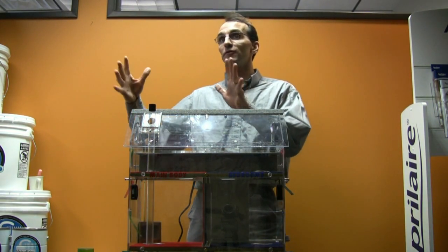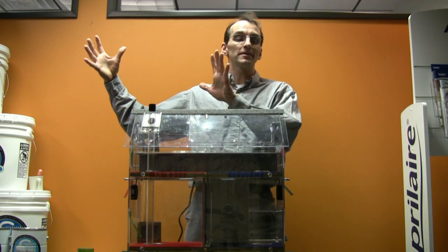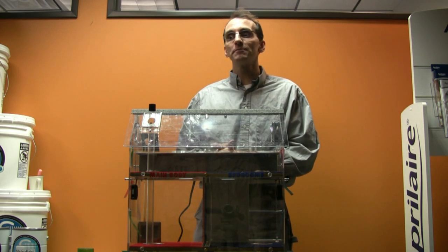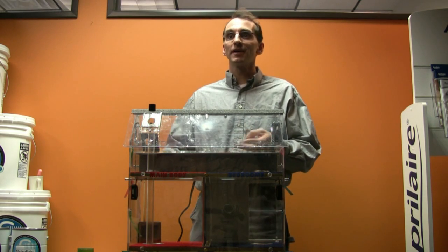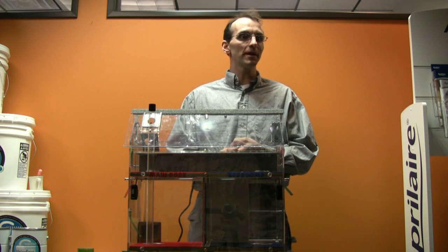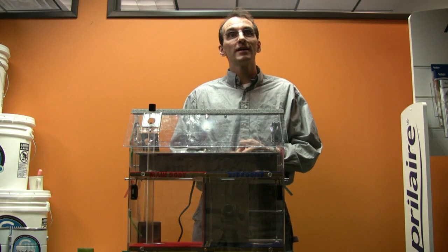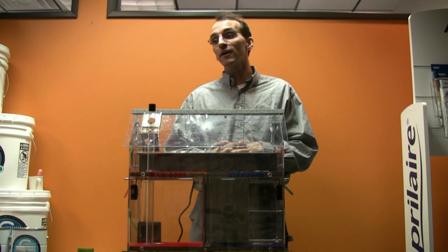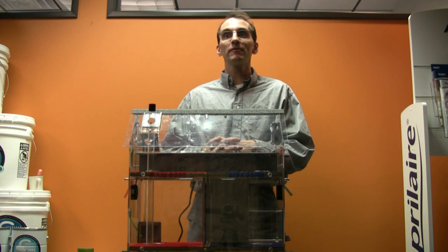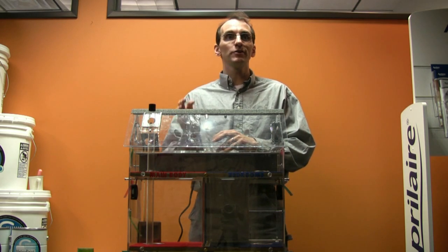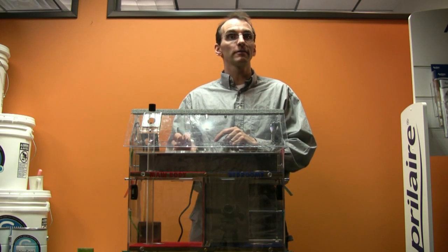Because if you look at that ductwork that is coming down to where your air filter is on your furnace, that's your return air ductwork. Oftentimes that's not taped. The enclosure where your filter goes may not actually be the best fitting in the world. If it's an old plenum that's been reconfigured for new ductwork, oftentimes that hasn't been fitted all that well. And frankly, it's typically a storage area, and people have banged and bumped into it a whole lot over the years as well. It's a very likely scenario that you have a leaky return air ductwork system in your house.